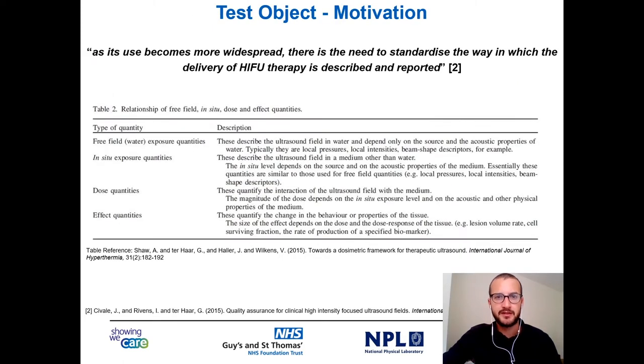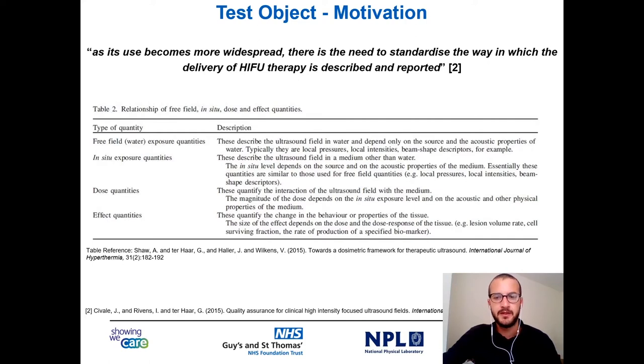Why do we need the test object? The use of HIFU is becoming widespread, and there is the need to standardize the way in which the therapies are described and reported. The main ultrasound field parameters, such as local pressure or local intensities, are well described in water. However, there is the need to define parameters for describing the interaction of the ultrasound fields in the medium. In other words, we need dose quantities, something equivalent to the absorbed dose or the equivalent dose that is used in ionizing radiation.